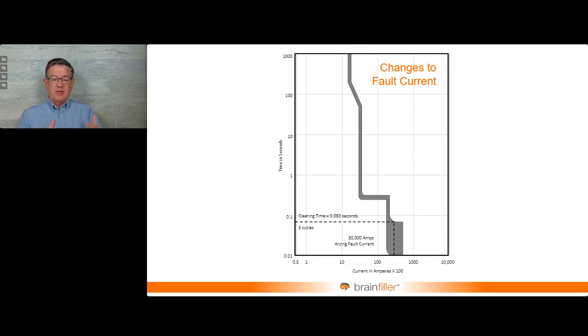This is a time current characteristic of a circuit breaker. And with 30,000 amps, this is going to operate instantaneously. But if there's a change, maybe the current's less, it's going to take longer to operate. And the clearing time, from my view, from being involved with this for a long time, is the single most important variable. If you double the clearing time, the incident energy doubles. Or halve it, and it's going to be halved.